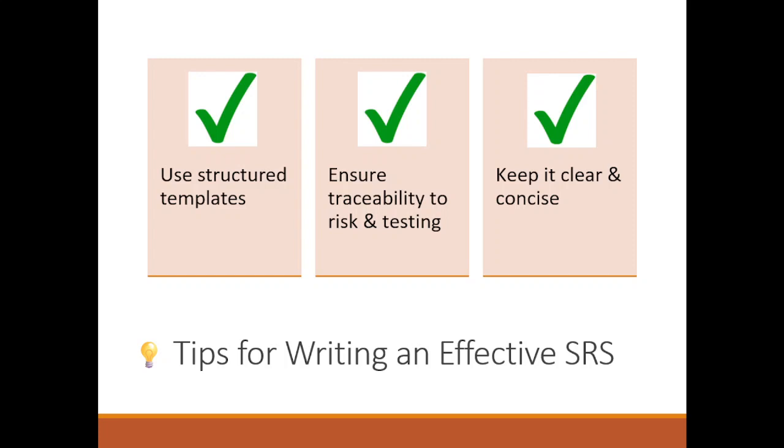Here are some tips for writing an effective SRS. Use structured templates to maintain consistency, and to ensure traceability between requirements, risk management, and testing. And keep requirements clear, concise, and testable to facilitate verification and validation.